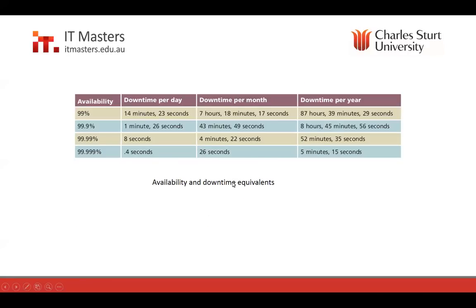Five nines is what we commonly quote. If we say our systems are 99% available, they have 14 minutes and 23 seconds of downtime per day, or 87 hours of downtime per year — which is quite high and would not be considered acceptable for a large company. The industry de facto standard is 99.999%, giving us downtime of just 0.4 seconds per day, 26 seconds per month, or five minutes and 15 seconds per year.